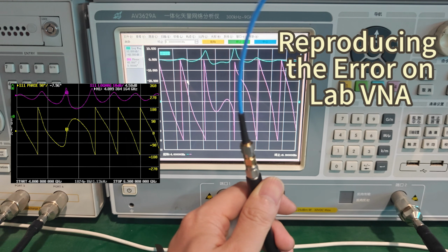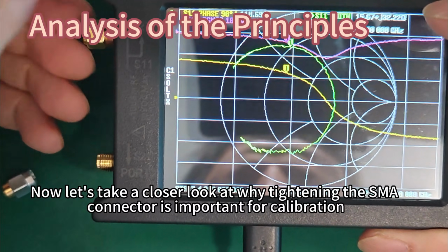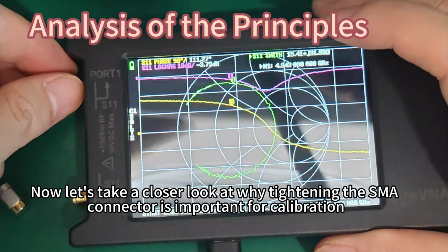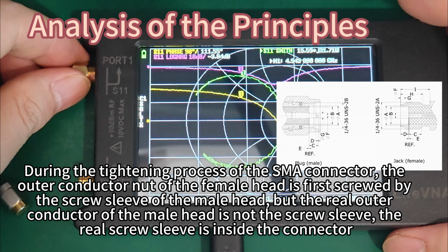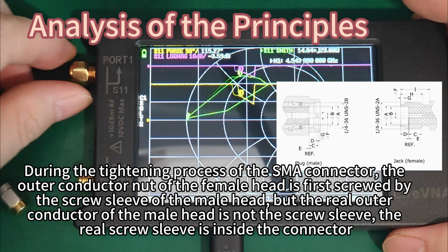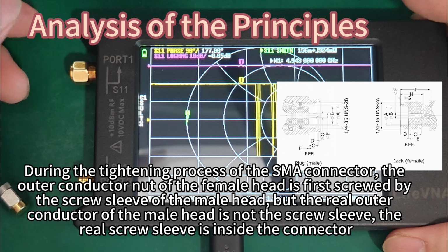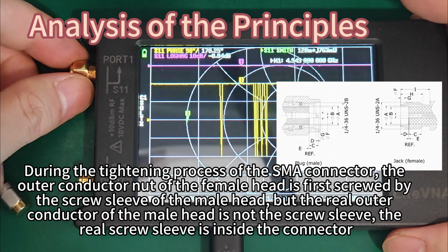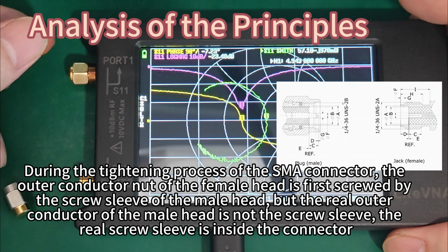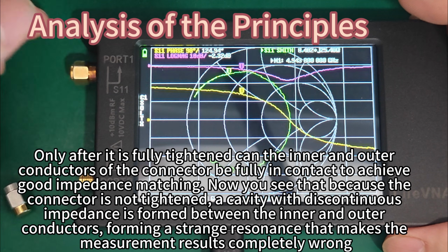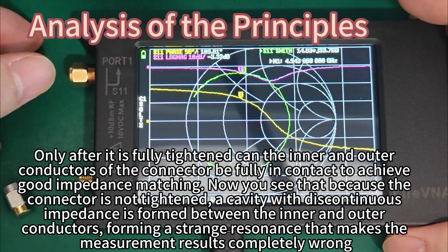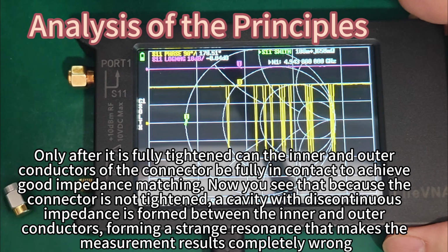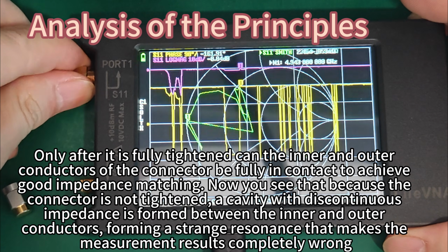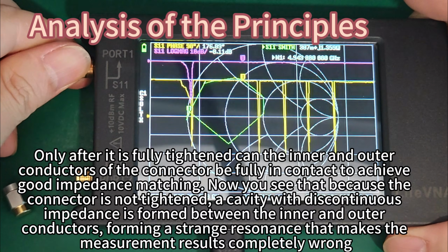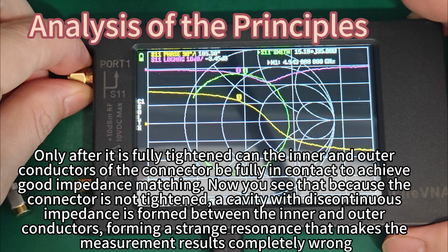Now, let's take a closer look at why tightening the SMA connector is important for calibration. During the tightening process of the SMA connector, the outer conductor nut of the female head is first screwed by the screw sleeve of the male head, but the real outer conductor of the male head is not the screw sleeve. The real screw sleeve is inside the connector. Only after it is fully tightened can the inner and outer conductors of the connector be fully in contact to achieve good impedance matching. Now you see that because the connector is not tightened, a cavity with discontinuous impedance is formed between the inner and outer conductors, forming a strange resonance that makes the measurement results completely wrong.